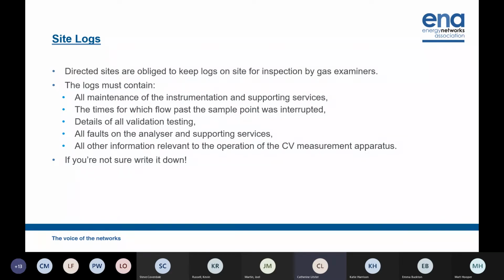Any testing that you're doing on site, so your ME2 tests, for example, should be written down, and what test you'll be doing each day, so the gas examiner, when they look at your log, can understand that you were doing a temperature test at that time on that day, and that's the reason why there's an alarm in the system. Any faults on the analyzer need to be written down with the times it was in fault, the reason for that fault, and what was done to correct it. And anything else, if you're not sure, my suggestion would be write it down. If you're working on site and you don't know if it needs to go in a log, write it down anyway. The gas examiner will go past it if he doesn't need to know about it.